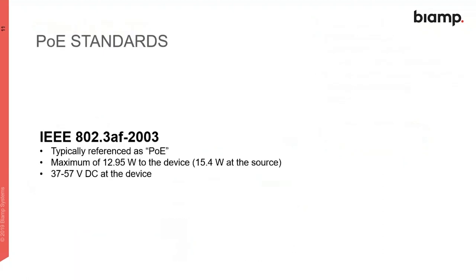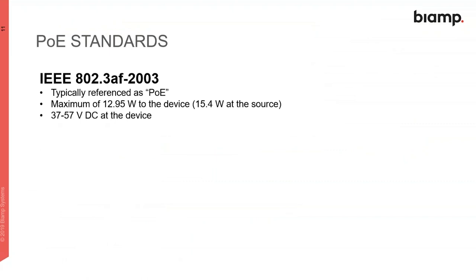PoE is a standard. 802.3af from 2003 is the standard most people are familiar with when they say PoE, and it delivers a maximum of almost 13 watts to the device. The device providing power gives you 15.4 watts, but to account for cable loss or DC voltage drop, we've got 12.95 watts guaranteed at the device. It's in a range between 37 and 57 volts, but most of the time it's 48 volts.